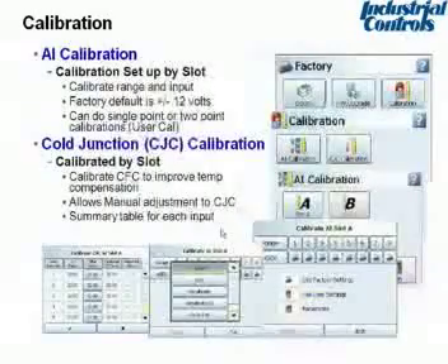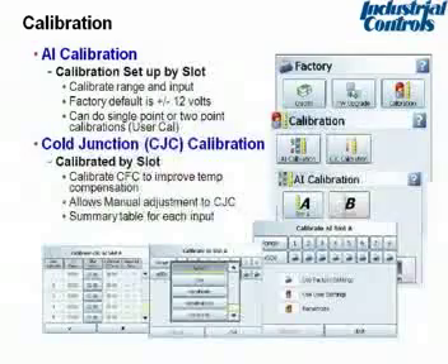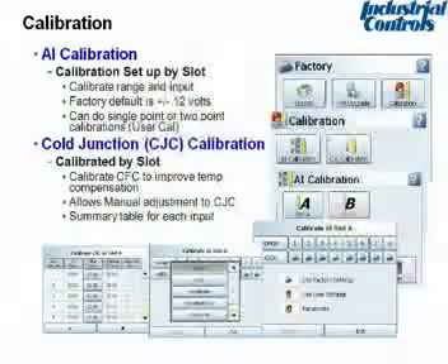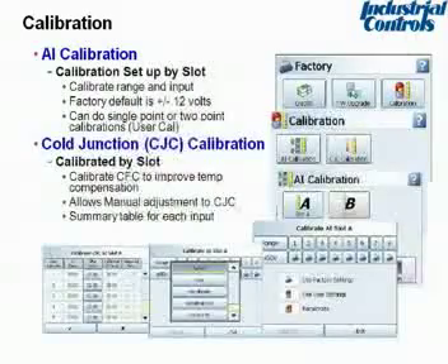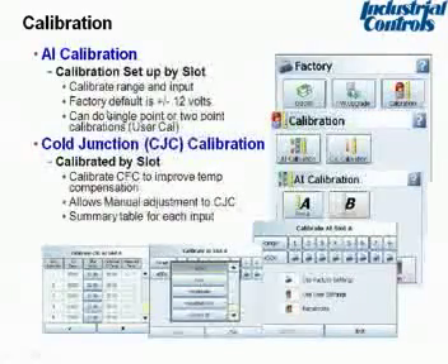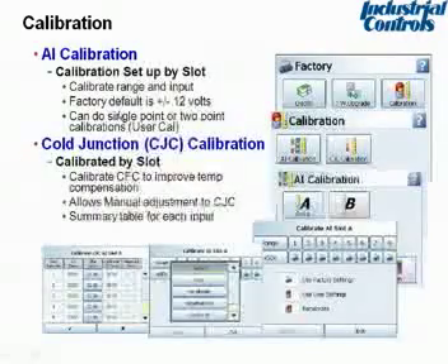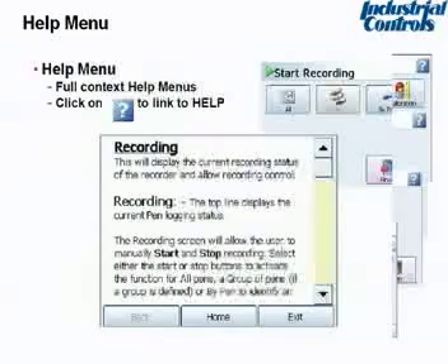Calibration - instead of looking at the paper chart, this is the calibration screen. So you would hook your plant standard into the back of the recorder like you would for the I/O of a paper recorder, and then go through the calibration screen to do the as-found, as-left adjustments. Very similar to paper recorder calibrations.